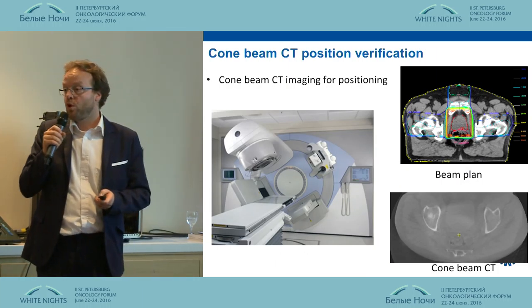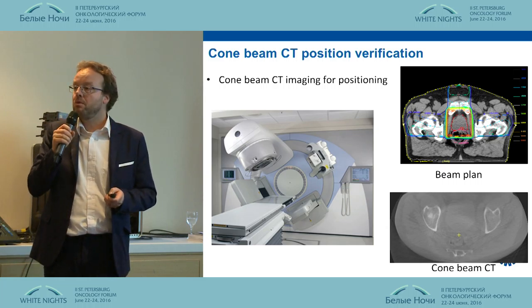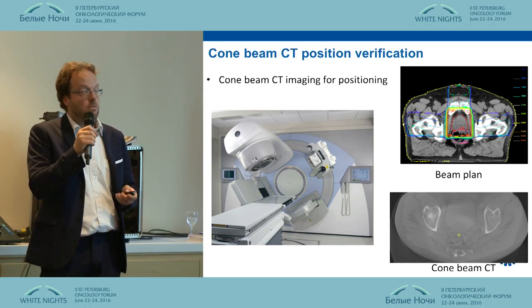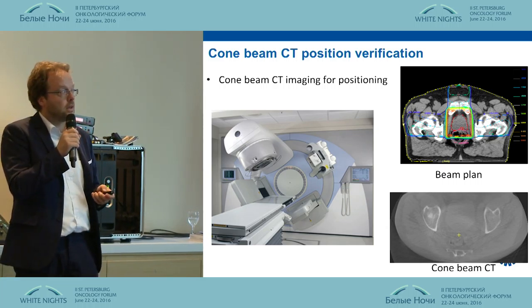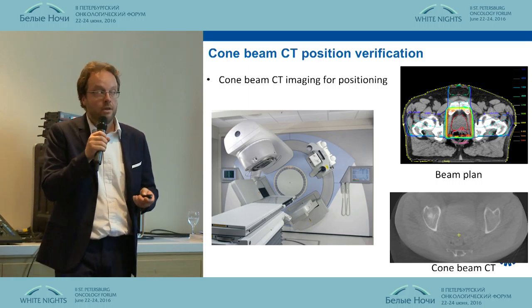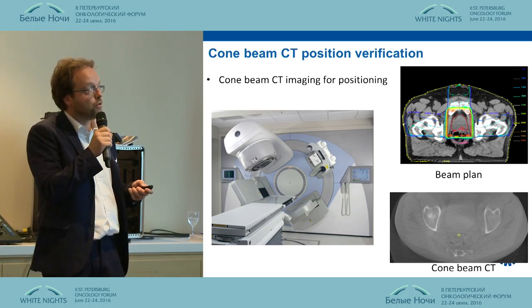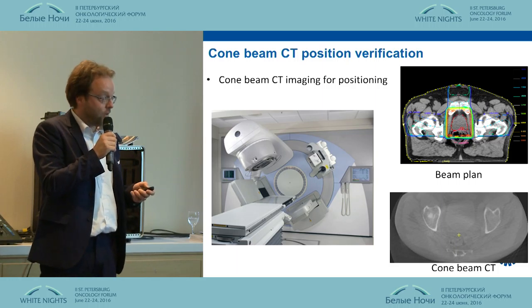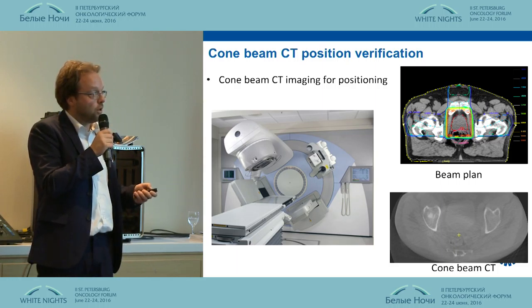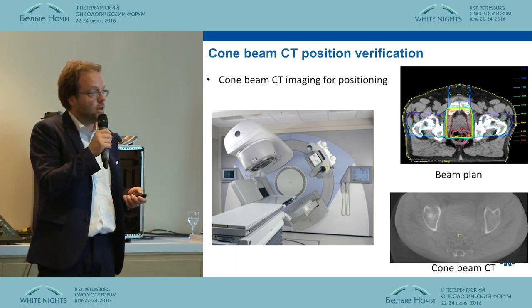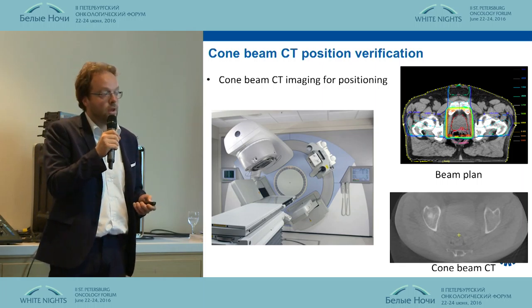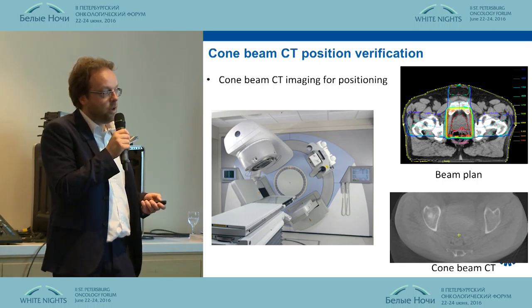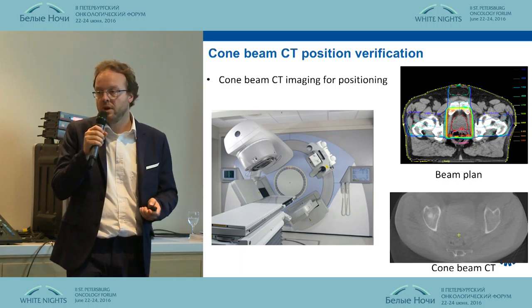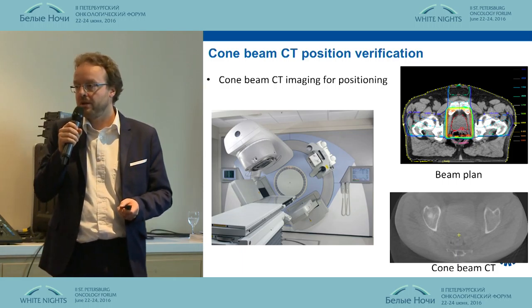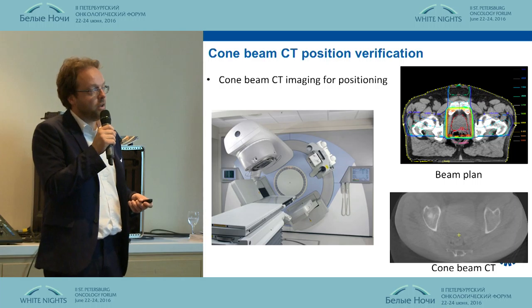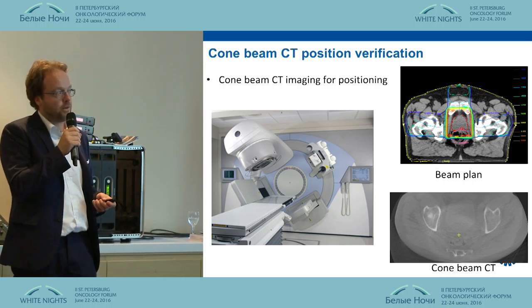More and more, we use cone beam. The example I gave previously was for prostate, but for other sites like head and neck, or even esophagus or pancreas, we use cone beam guidance. This is orthogonal to the megavolt image, using kilovolt imaging, producing images where you can see bony anatomy. The soft tissue contrast is of lesser quality than standard CT, but it suffices for position verification.